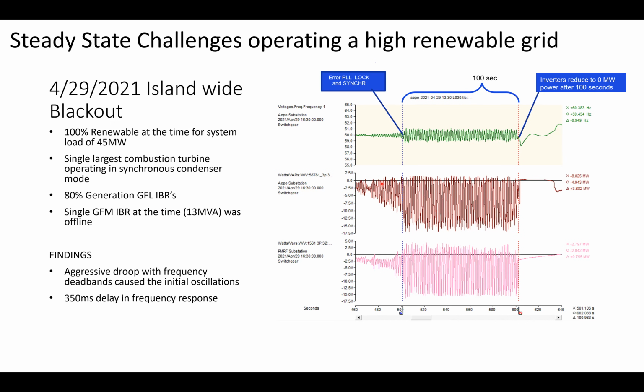What we found was basically something that you might see in some of the modeling that you have been doing: our grid following inverters, with their delay, caused an oscillation in frequency, which caused a further magnitude of amplification of oscillation between our grid following inverters across the island. And so we start getting into these power swings between our synchronous generation and our grid following inverters, to the point here in blue on this dashed line where we actually start load shedding per our load shed scheme, which then drives our system load to drop off, causing frequency to go high, causing grid following inverters to pull back on their real power, which continues to drive our synchronous machines to push back out as a response.